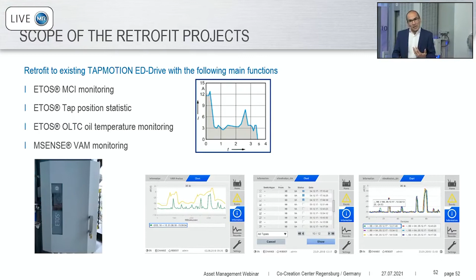Every station is very large, with over 28 transformers on each station, and therefore a sound, meticulous project was created. And during that retrofit, we also introduced and retrofitted a second measurement, the motor current index, the tap motion statistics, as well as the oil and OLTC temperature monitoring. A few additional signals and values which can be integrated into MSense VAM to make the OLTC monitoring more complete.